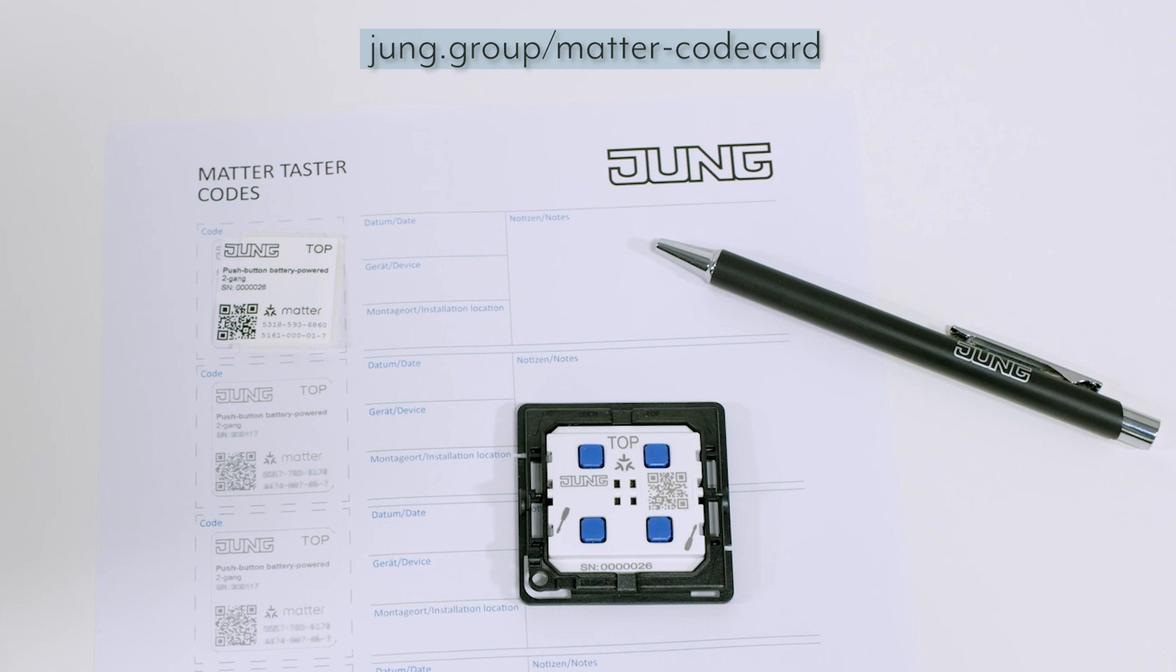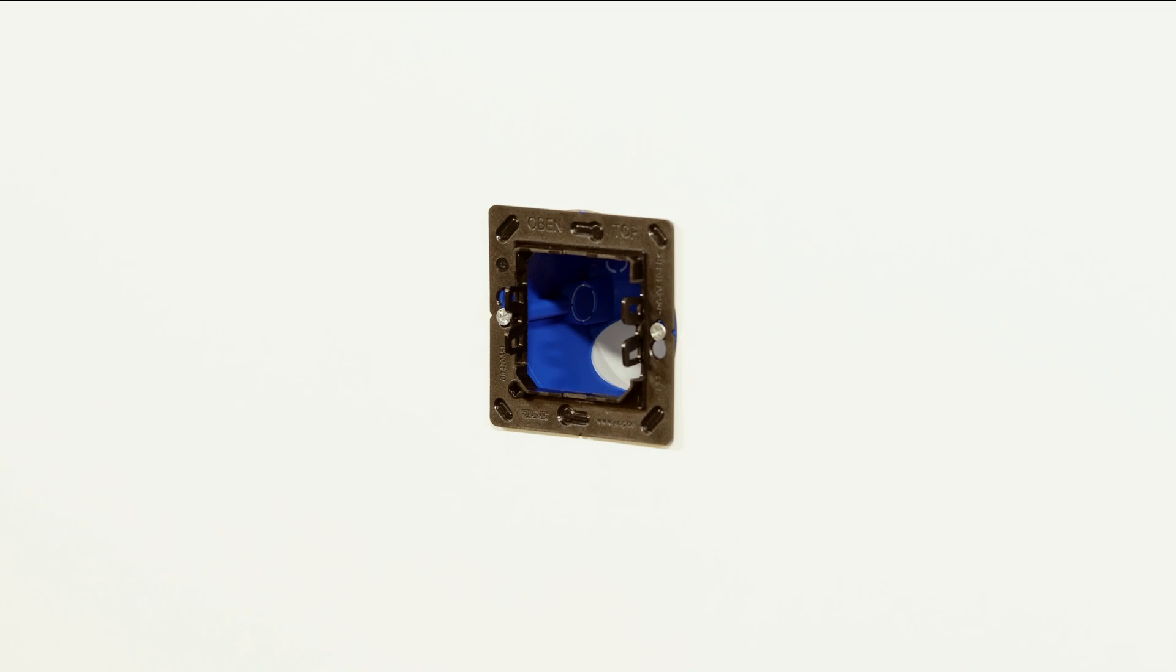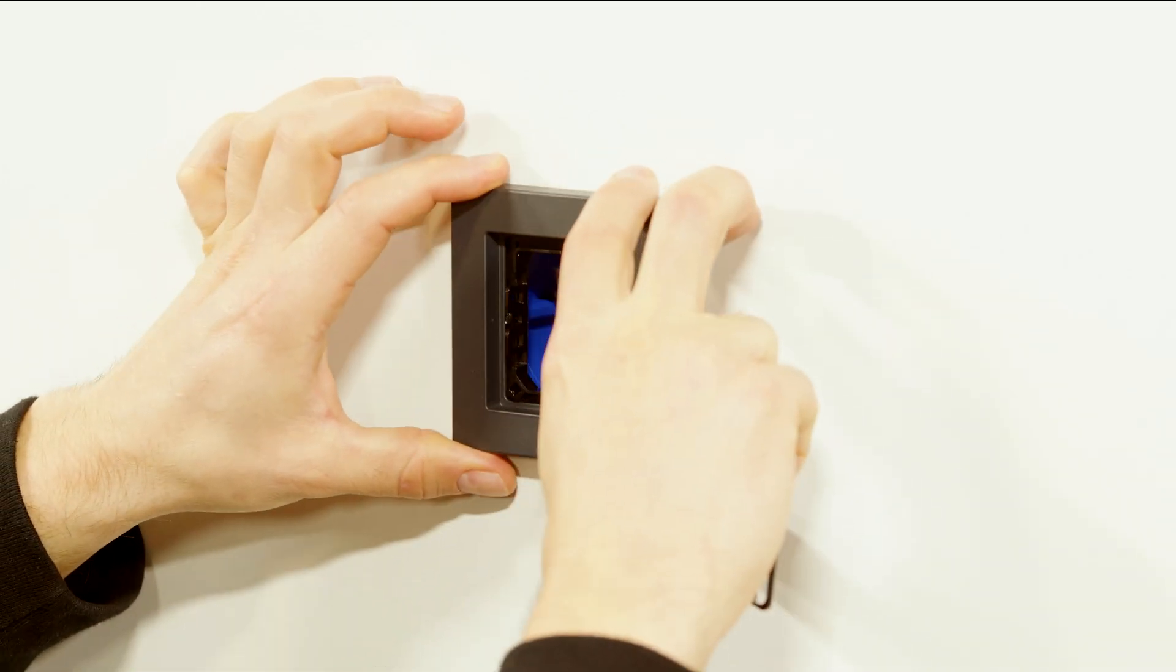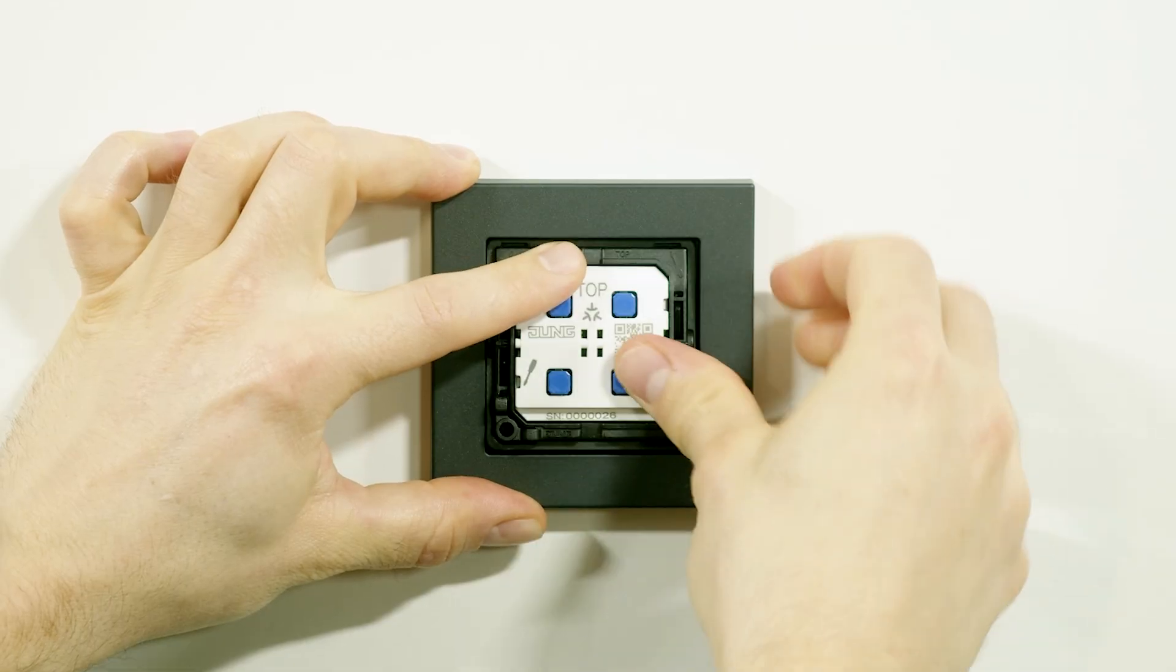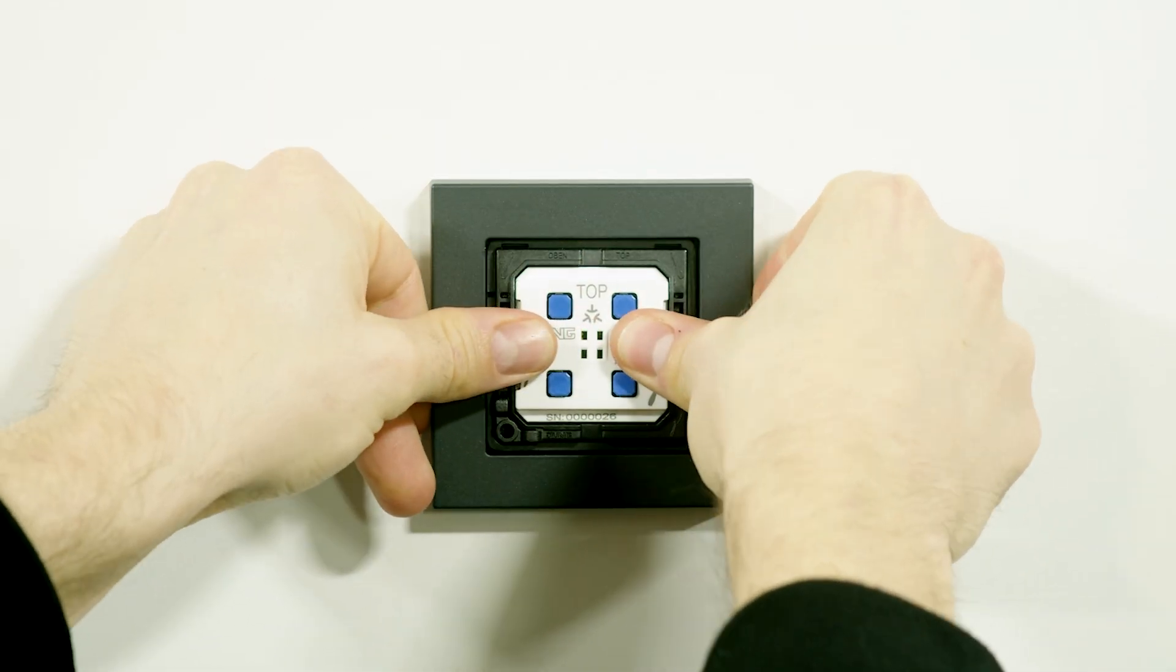The primary code card is a copy of the lasered QR code on the radio module. It serves as a fallback option if the QR code on the module itself cannot be read or for devices that are difficult to access, such as lights on the ceiling. Attach the radio module together with the design frame to the base plate. Make sure the top marking is facing upwards.